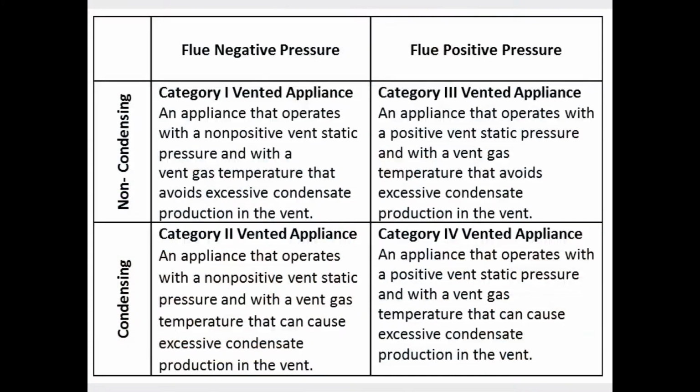But again, what is going to be the pressure inside the vent? Are you relying on Mother Nature or are you going to shove it out? And then are you going to have low flue temps or are you going to have high flue temps? That is the driving force in deciding category 4 material.